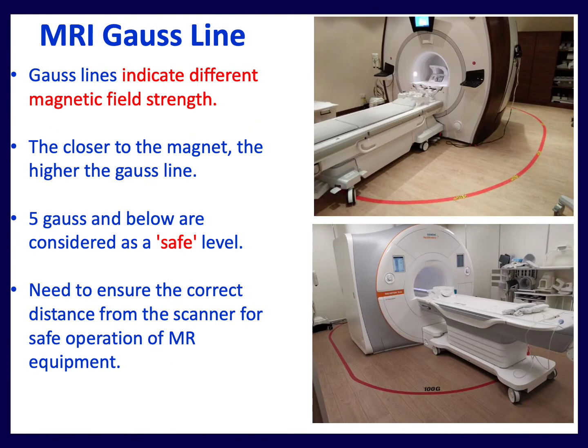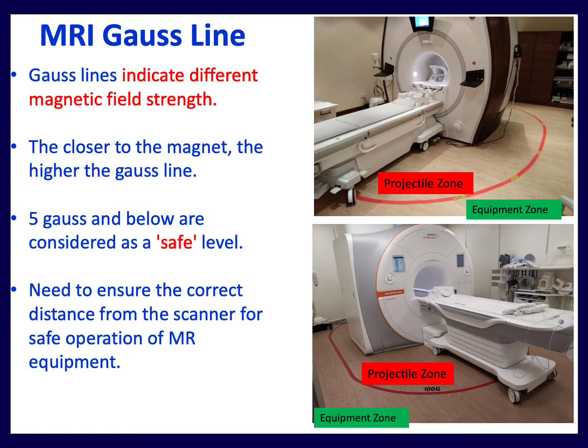The MRI Gauss line is another key thing that is drawn on the floor, and these Gauss lines indicate different magnetic field strengths. The key thing to note is that the closer you get to the magnet, the higher the Gauss line is. So 5 Gauss and below is considered a safe level, outside this red line. You need to ensure the correct distance from the scanner for safe operation of MR equipment as well. And this is important. For all staff who go in, when you dock the equipment under the supervision of the radiographer, you shouldn't move it again at all unless you have permission from that radiographer. Inside the red zone is a potential projectile zone, and the equipment should be outside that red line.